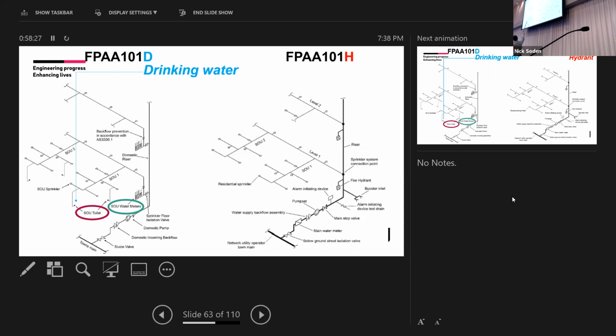So basically the sole occupancy unit, the toilet, is coming off the residential system. These will go to the apartments for the toilets, hand basins and shower, etc. And then there's a separate line which will be a feeder into every sole occupancy unit. At the end of the line, they are putting the water to the toilet as an alarm bell, I suppose, and to keep flushing the system. So if you look at this system here as well, it's all coming off the town's mains. It would obviously have to be hydraulically designed to ensure the right pressures are coming out of every fixture, for both the showers, toilets, and also the sprinkler system.